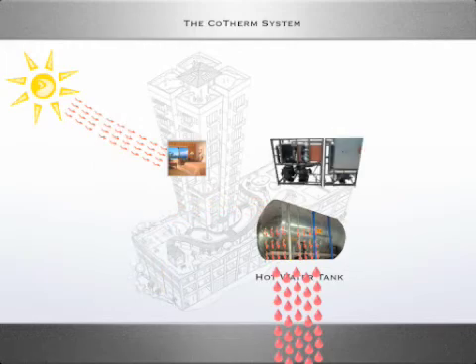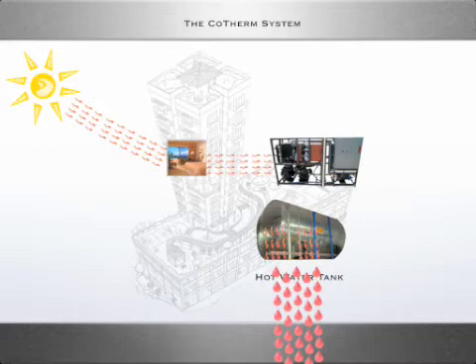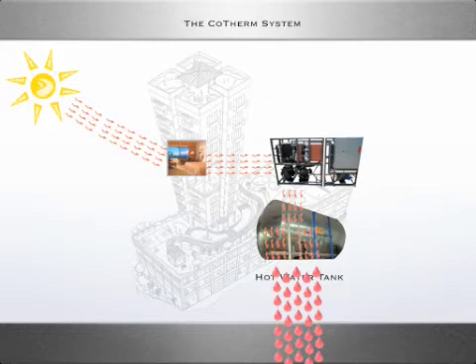Now it's time for Cotherm. We can direct the heat from the air conditioning system to the Cotherm unit, where the heat is boosted to the desired temperature before being transferred to the water in the hot water tanks. Similar to a heat pump, we have hot water without fuel. The difference is, while using Cotherm, the electric bill remains steady.